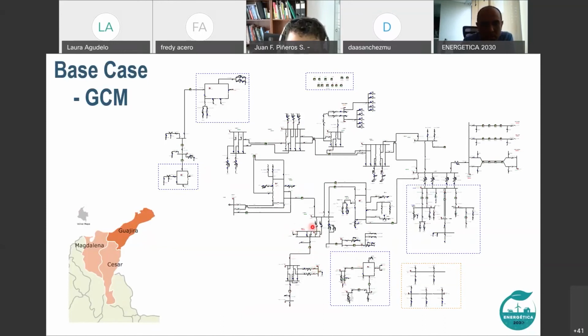Then, as you can see, we were modeling all these substations. And we were considering the scenario Laura was presenting, which we call the P12, because it's the time we will have the maximum point of inverter-based generation. We were modeling all the substations and generation connected to this area. We have here the power plant Termo Norte, here Guajira 1 and 2, and these are the power plants we have in this area, together with the new inverter-based generation in Cuestecitas. And besides the P12, we were also running simulations in the P04.